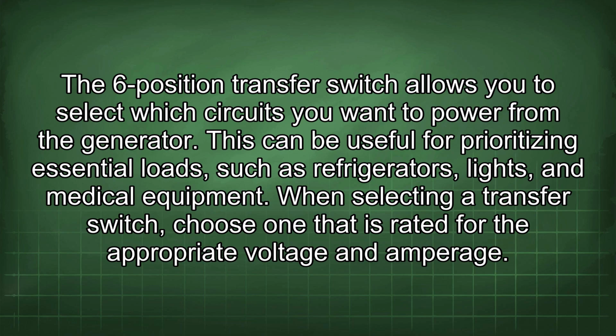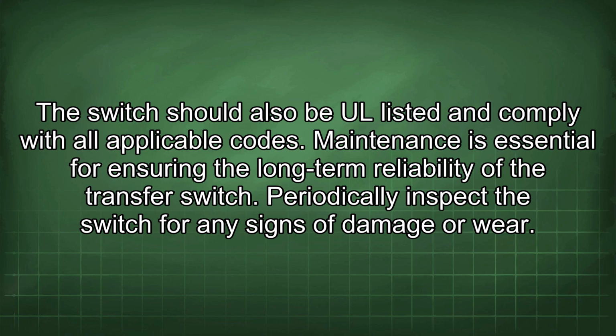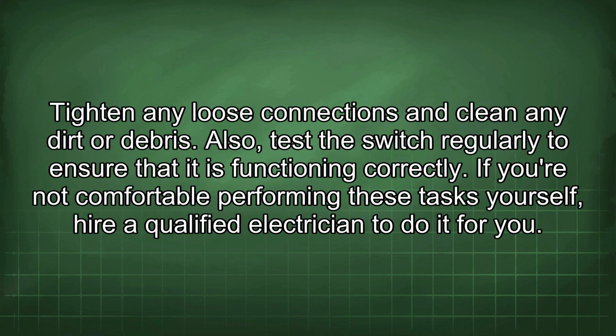When selecting a transfer switch, choose one that is rated for the appropriate voltage and amperage. The switch should also be UL listed and comply with all applicable codes. Maintenance is essential for ensuring the long-term reliability of the transfer switch. Periodically inspect the switch for any signs of damage or wear. Tighten any loose connections and clean any dirt or debris. Also, test the switch regularly to ensure that it is functioning correctly. If you are not comfortable performing these tasks yourself, hire a qualified electrician to do it for you.